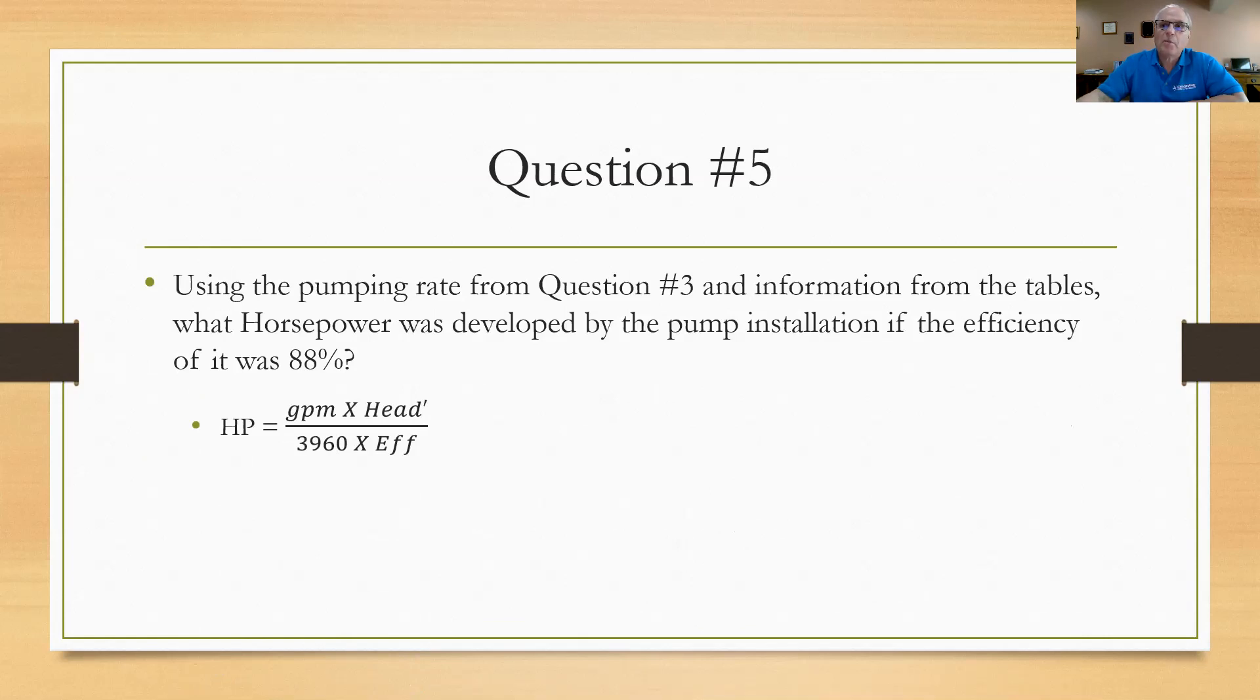Anyway, getting back to the problem, the horsepower is going to be 1,750 gallons per minute times that 90-foot head, which you had to find from going into the tables, divided by 3,960 and the 88 percent that they gave you turned into a decimal, which is 0.88. And I would come up with about 45.2 horsepower. Okay, those were certainly simple. I promise you they're going to get a little bit more complicated as we go on through the plant at Bacon Road.